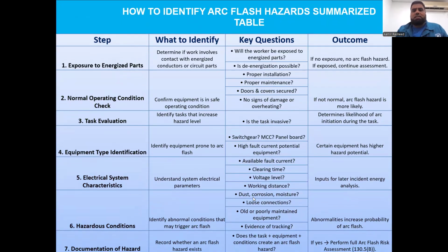How to identify the arc flash hazard, summarized. This is a typical table that I'm sharing with you, giving the different steps. Am I exposed to an energized part? What are the normal operating conditions, like poor installation, maintenance, is there any dust? Then we evaluate the task to identify the equipment prone to arc flash, either a switchboard or an MCC panel board.